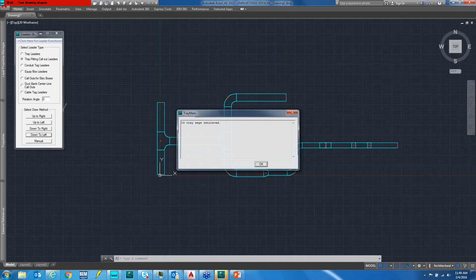Frequently when we're modeling cable tray, we're following the path of a pipe rack or pipe chase, so we'll have multiple levels of tray stacked. I could go in and reset my AutoCAD elevation and start modeling the tray as I went up, but the easy way is to use the stack command. The next level up will be medium voltage, and the level above that will be high voltage, with a 24-inch separation between tray levels.